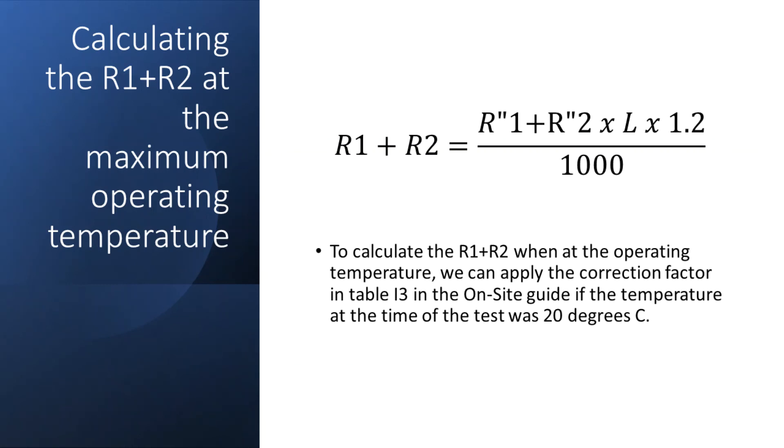So this calculation can be useful if you ever need to verify what the R1 plus R2 should be when carrying out electrical testing, and you can also use this to verify the measured ZS by adding the calculated value for R1 plus R2 to the measured value for ZE.